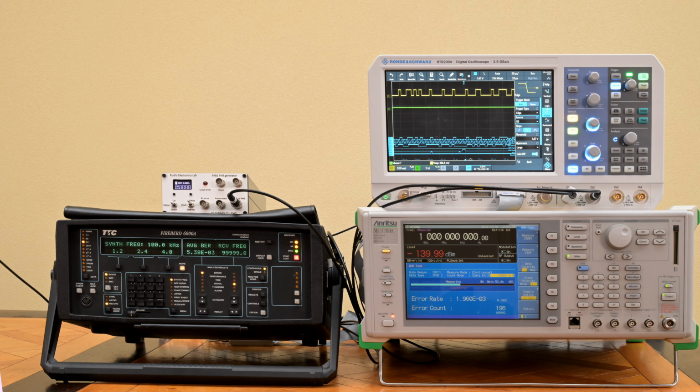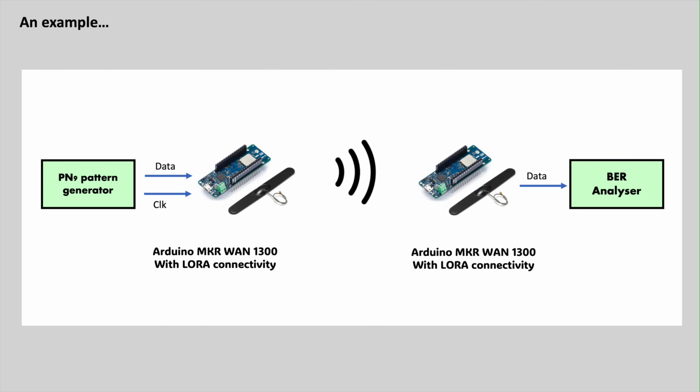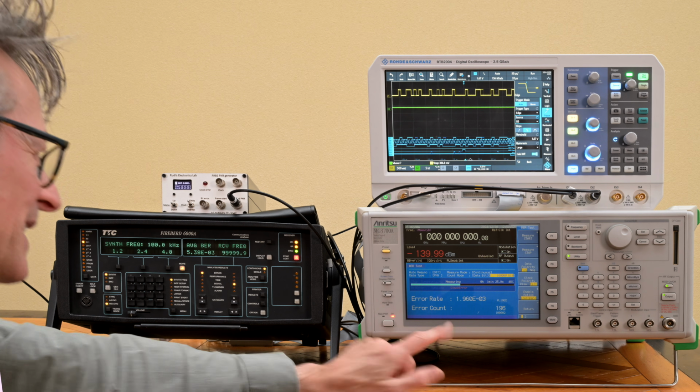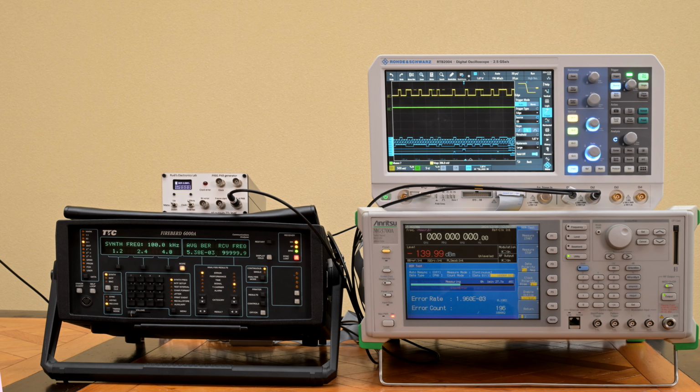And why I'm excited about that is because it would also allow me to do some testing when I do wireless connections via all types of Arduino-type setups with signals, with LoRa-type signals, whatever I want to play with, because then often I don't have a clock anymore after getting it from a mobile unit. And the recovery possibility here is really something that I very much value. So that is a big plus over most of the BER testers on the market. It can work without a clock signal.